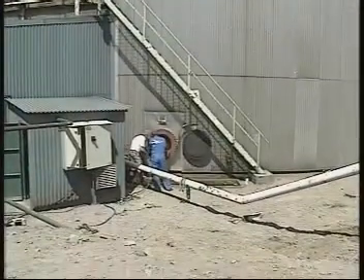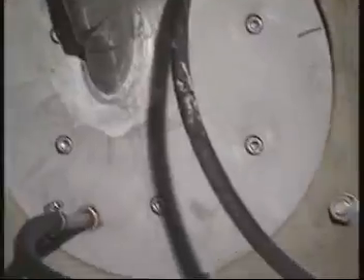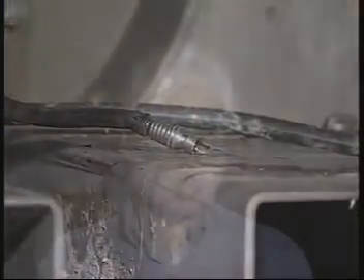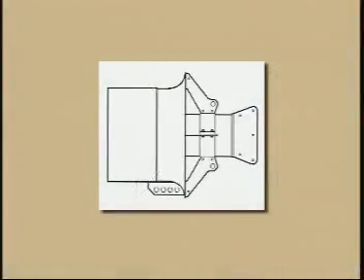Additional cooling can be provided to the flange-mounted mixers by using a cooling jacket in which cool water can be circulated. As I mentioned, the mixer must always be submerged to get sufficient cooling and for proper heat transfer to occur. And if the yield stress of the mud is higher than the mixer was designed for, the flow around the mixer will be too weak.